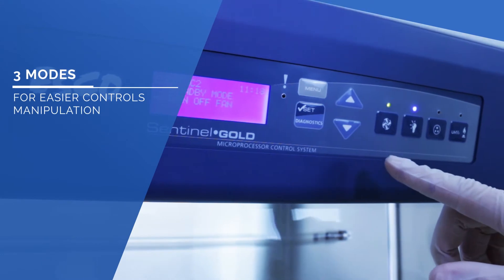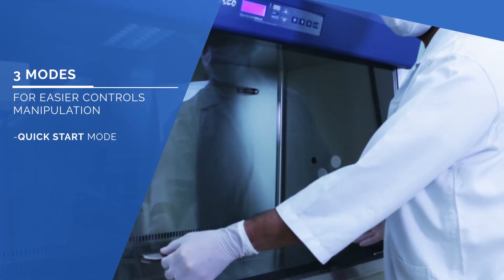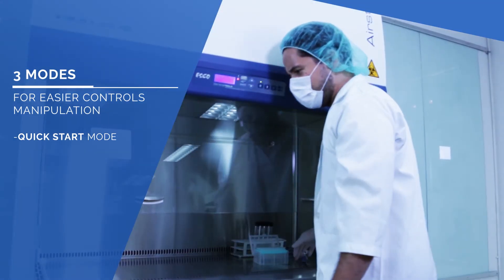And has three modes for easier controls manipulation such as Quick Start Mode that allows automatic turning on of the fan and fluorescent lamp when the sash is raised to its working height.